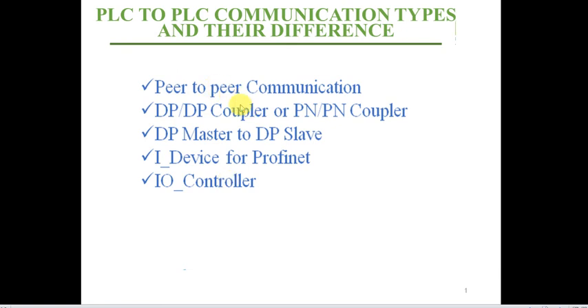The first type is peer-to-peer communication, where two PLCs are connected directly and share data — they must be under the same network. The second type uses a coupler, like a DP coupler for Profibus and a PN/PN coupler for Profinet. The third type is master and slave, which is for Profibus.